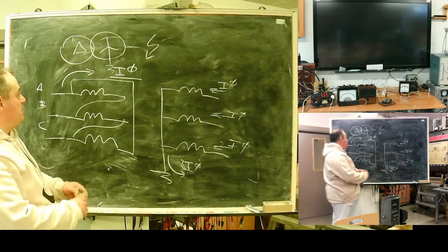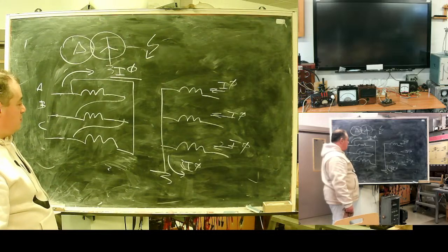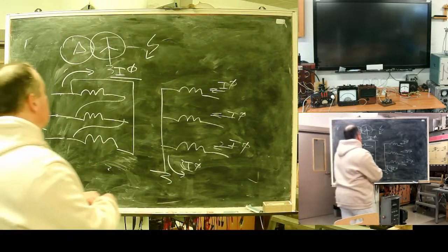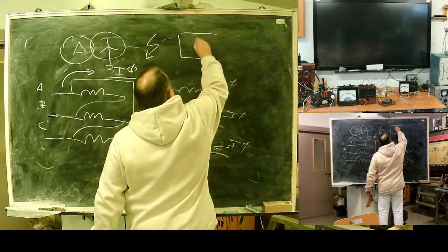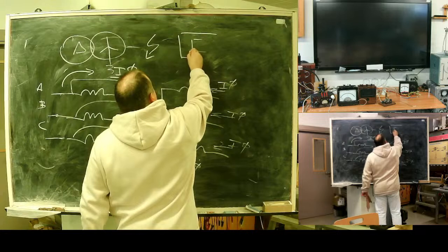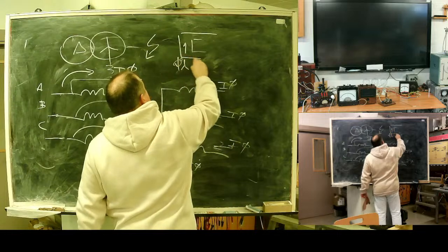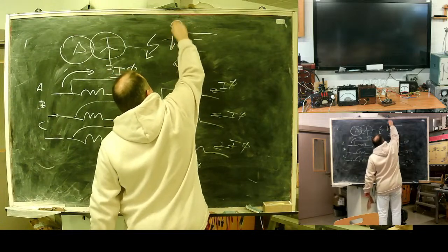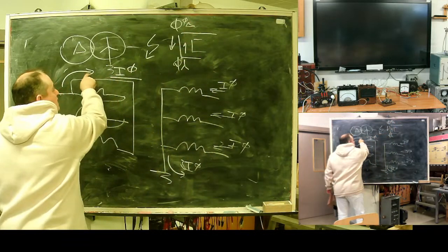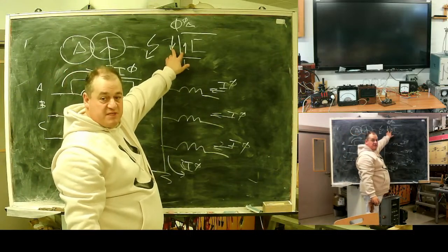That means that in analyzing zero sequence current magnetic flux, we have a transformer leg, delta, zero sequence flux, and opposite zero sequence flux from this circulating current. The sum of zero sequence flux in the leg will be zero.